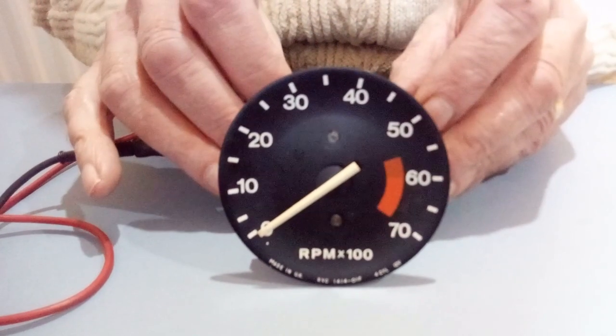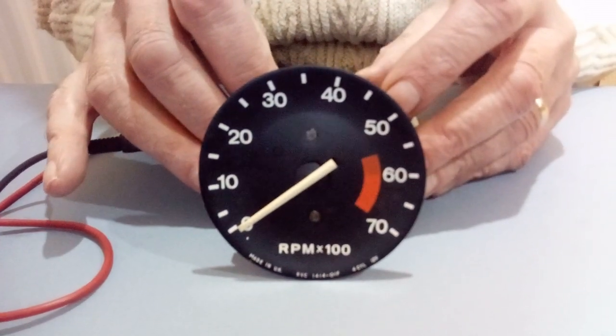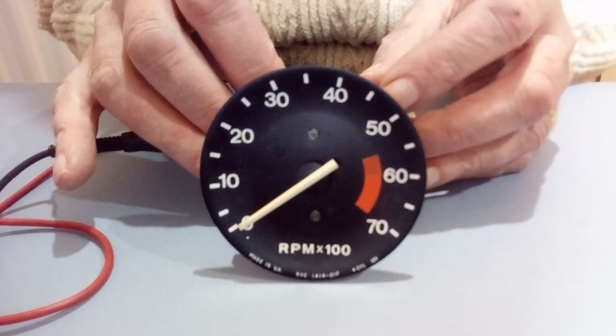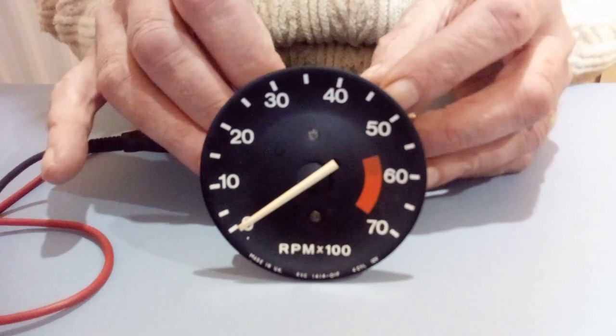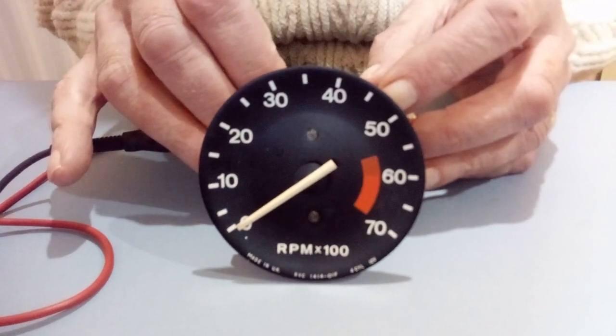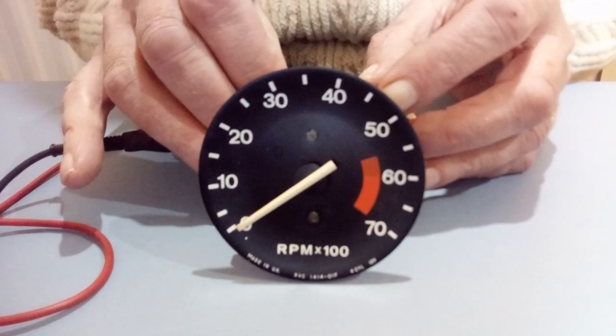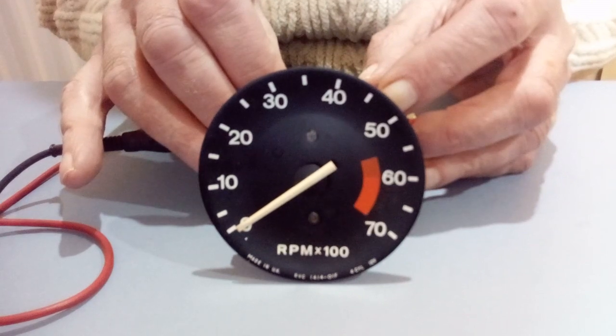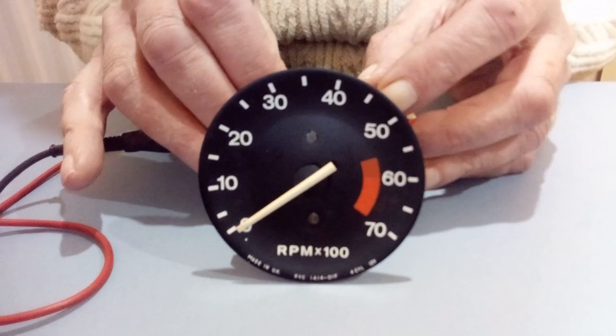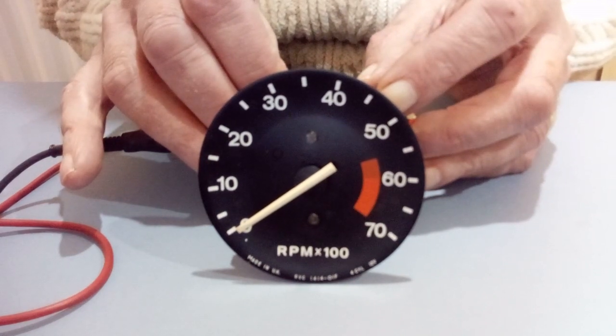Okay, so to start the calibration process, we hold the calibration button in for at least 2 seconds, and when I release it, you'll see that the needle will start to move very slowly around the scale. It takes a few seconds, maybe 15 seconds or so, before that starts to happen. And when it does start to move, we're going to stop it at several points, the calibration points, to teach the electronics the positions on the scale.